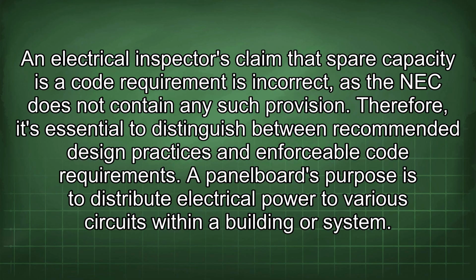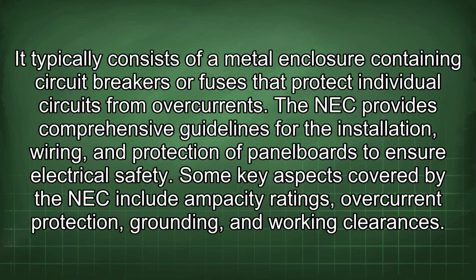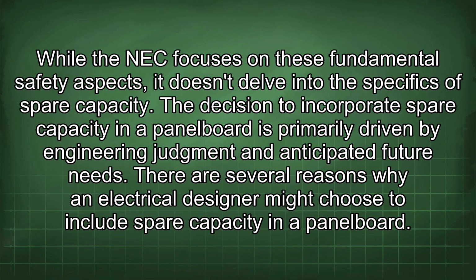A panelboard's purpose is to distribute electrical power to various circuits within a building or system. It typically consists of a metal enclosure containing circuit breakers or fuses that protect individual circuits from overcurrents. The NEC provides comprehensive guidelines for the installation, wiring, and protection of panelboards to ensure electrical safety. Some key aspects covered by the NEC include ampacity ratings, overcurrent protection, grounding, and working clearances. While the NEC focuses on these fundamental safety aspects, it doesn't delve into the specifics of spare capacity. The decision to incorporate spare capacity in a panel board is primarily driven by engineering judgment and anticipated future needs.